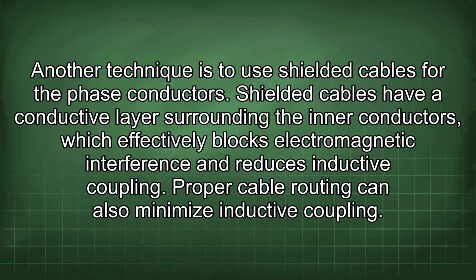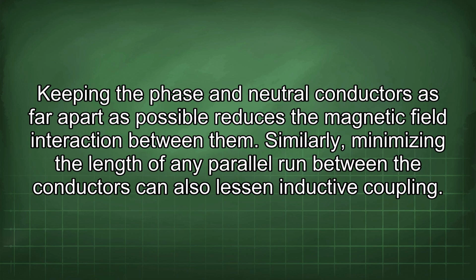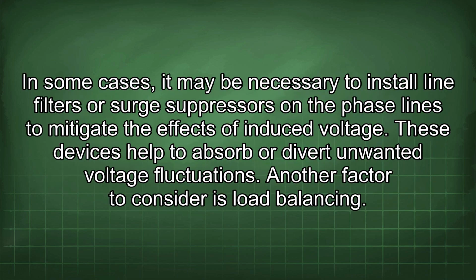Shielded cables have a conductive layer surrounding the inner conductors, which effectively blocks electromagnetic interference and reduces inductive coupling. Proper cable routing can also minimize inductive coupling. Keeping the phase and neutral conductors as far apart as possible reduces the magnetic field interaction between them. Similarly, minimizing the length of any parallel run between the conductors can also lessen inductive coupling. In some cases, it may be necessary to install line filters or surge suppressors on the phase lines to mitigate the effects of induced voltage. These devices help to absorb or divert unwanted voltage fluctuations.